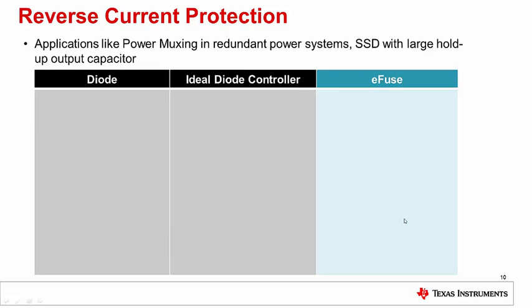Reverse current protection. Reverse currents can flow through the system when the voltage at the output is higher than at the input. In applications such as power muxing for redundant power systems or SSD with a large hold-up output capacitor, there will be a risk of large reverse currents when the input power is disconnected. These reverse currents can damage internal circuitry or system power supplies if they are not limited. Let's see how this can be achieved.